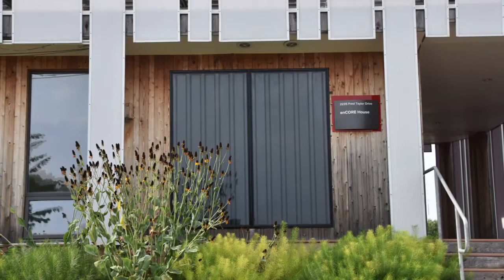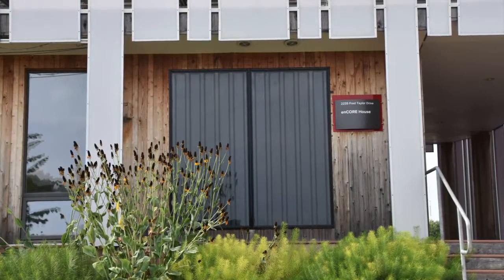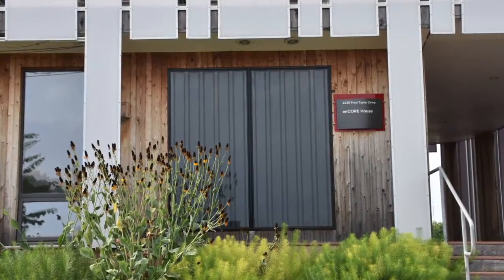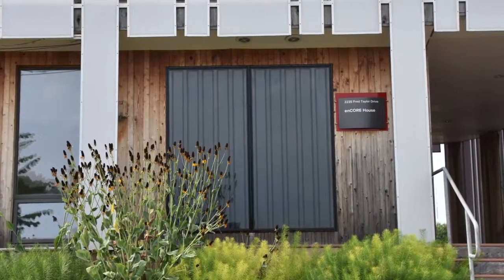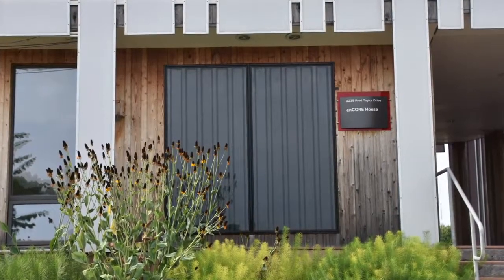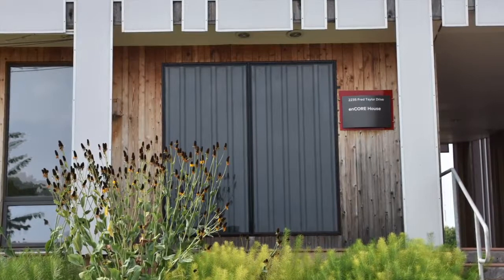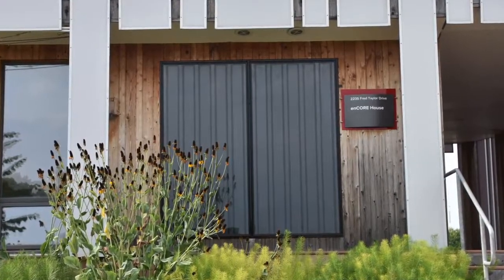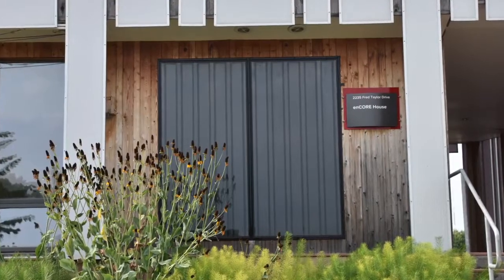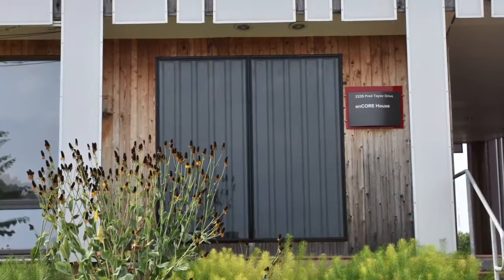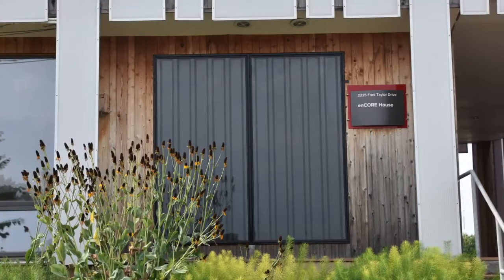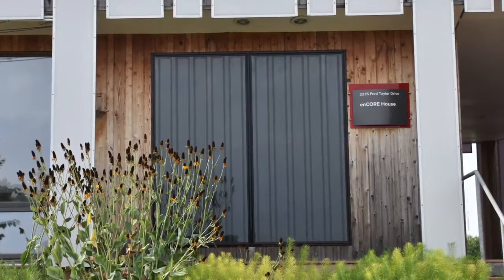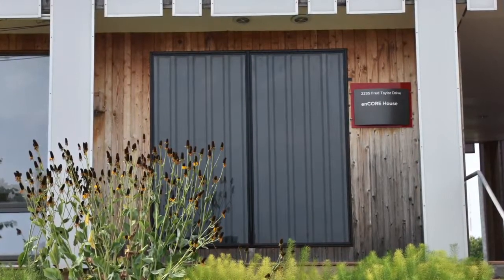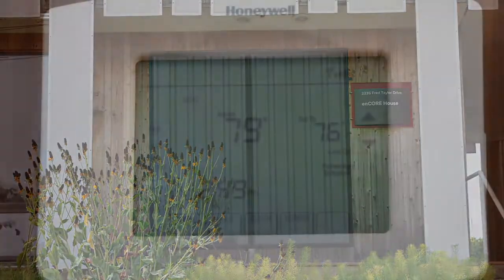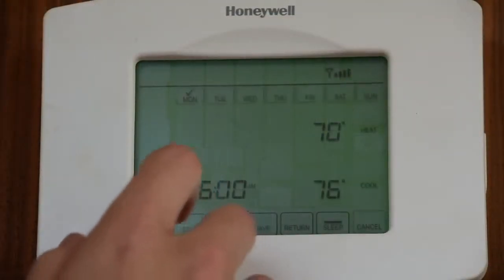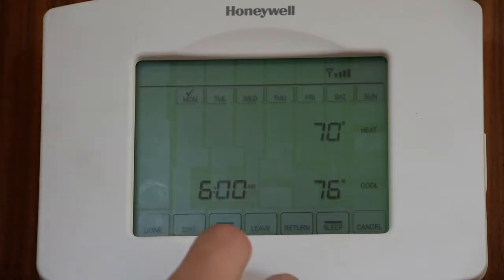The solar thermal hot air collector is located on the southern wall of the home to maximize the energy potential of the system. What you see here are the 2 large solar thermal collectors. These collectors are heated by direct absorbed radiation, which transfers heat to air that passes over them. These collectors can absorb up to 16,000 British thermal units per hour at 90 to 100 degrees Fahrenheit. The system results in a 10% heating load reduction and a 9% cooling load reduction. The system is integrated into a smart control system that can be controlled using a touchscreen located in the home or by an occupant's smartphone.